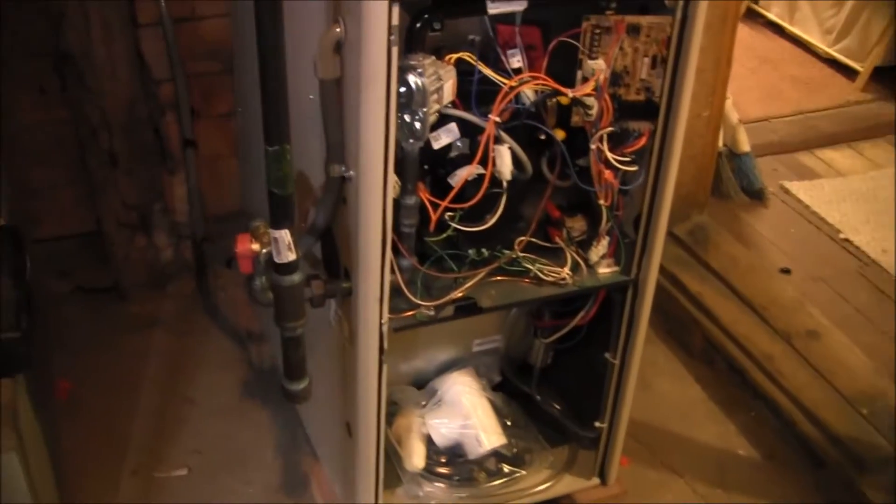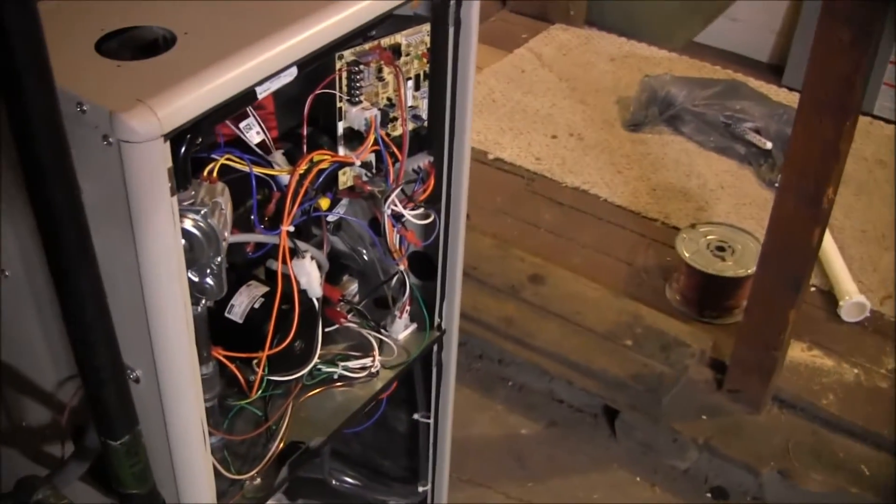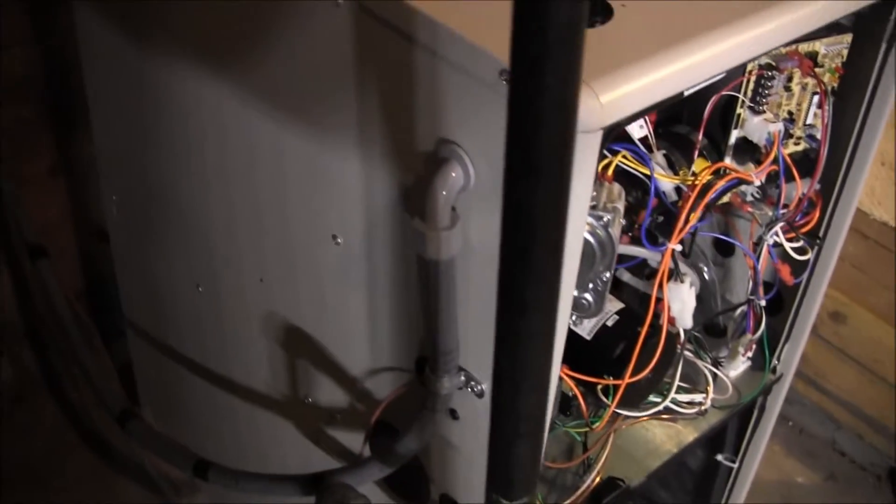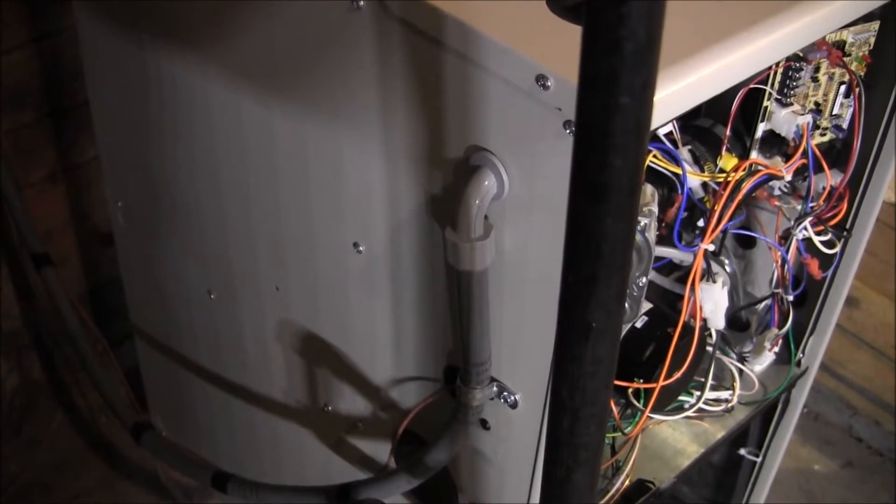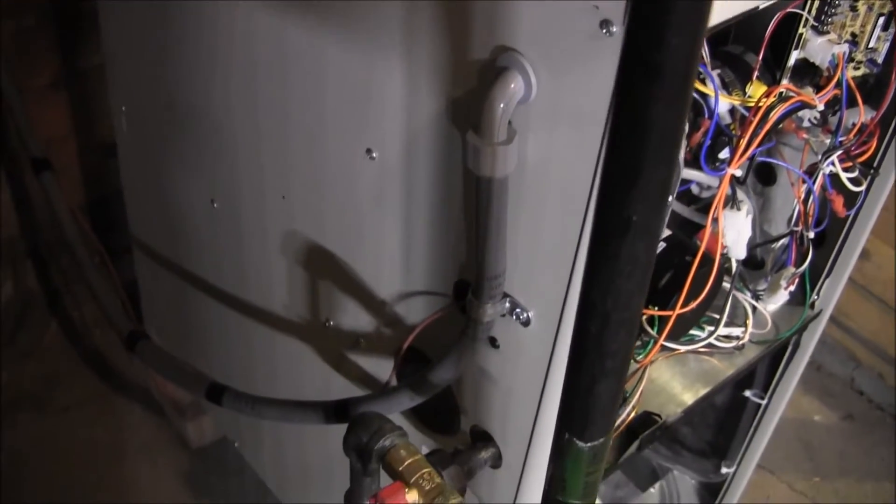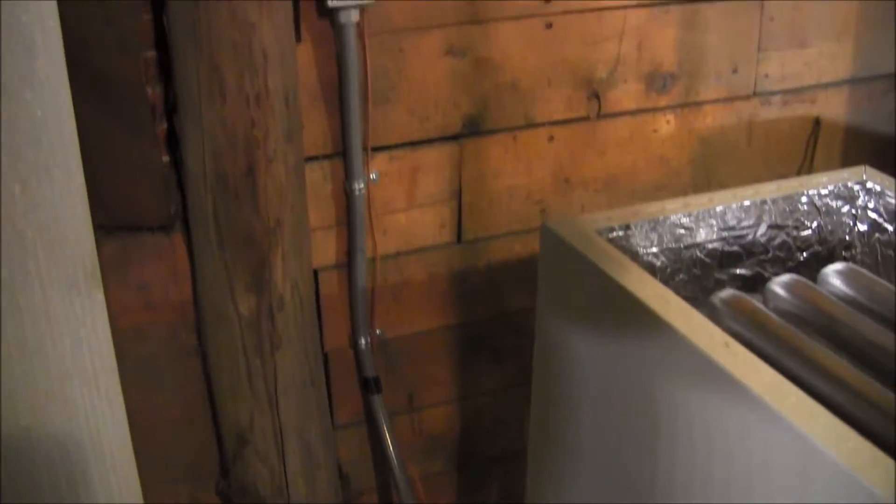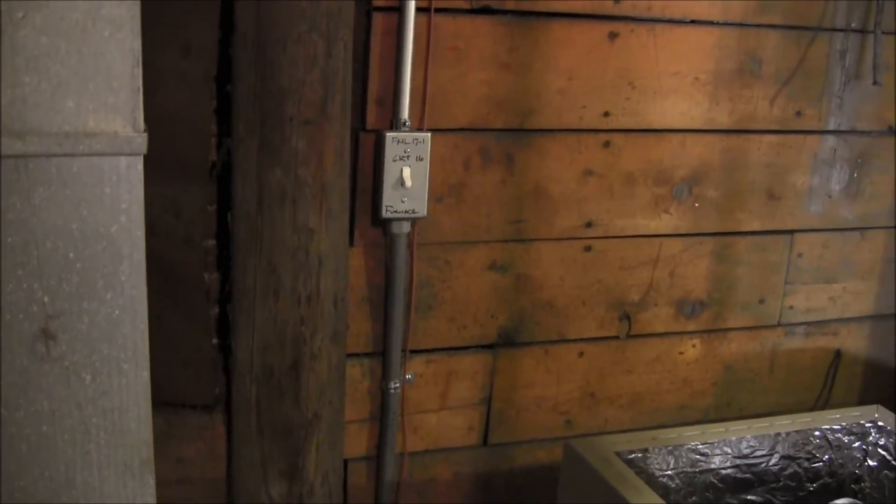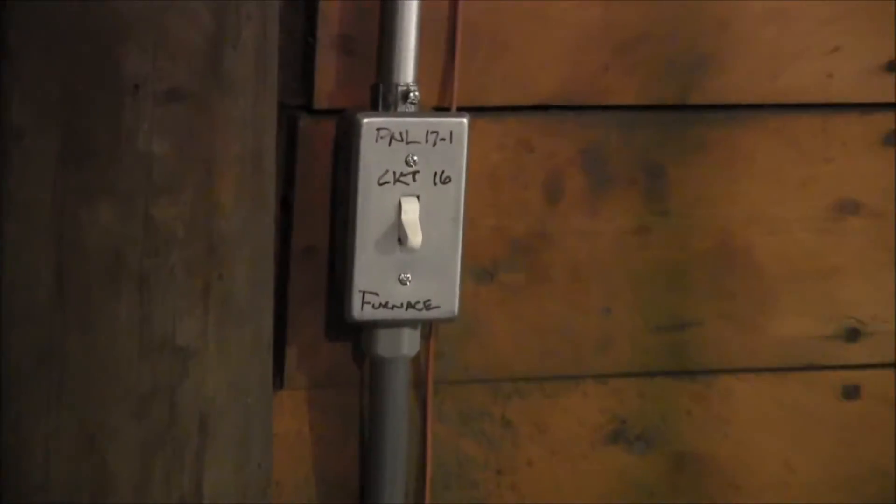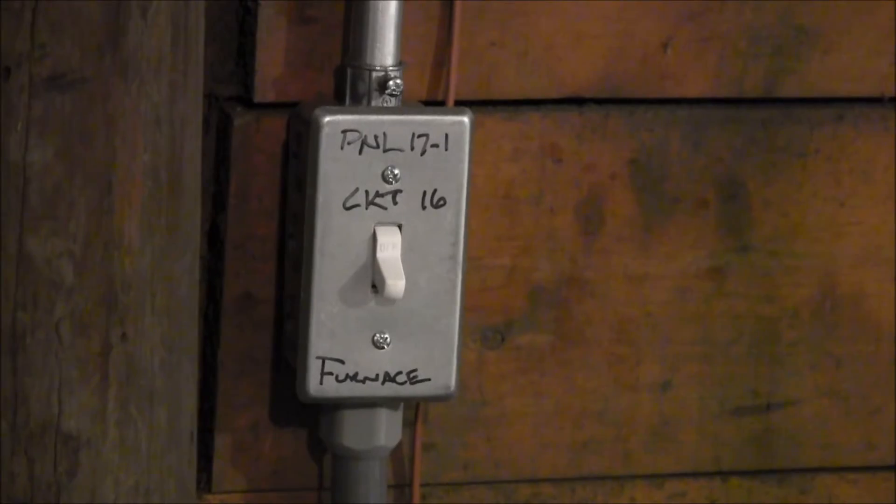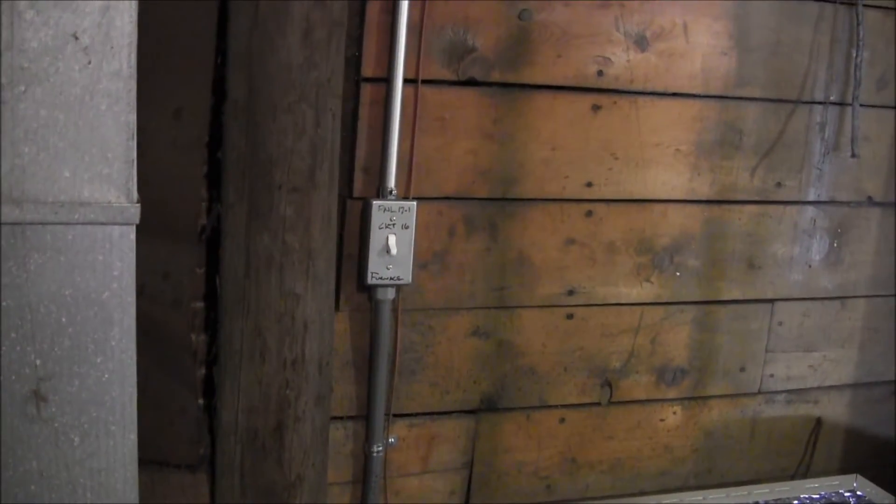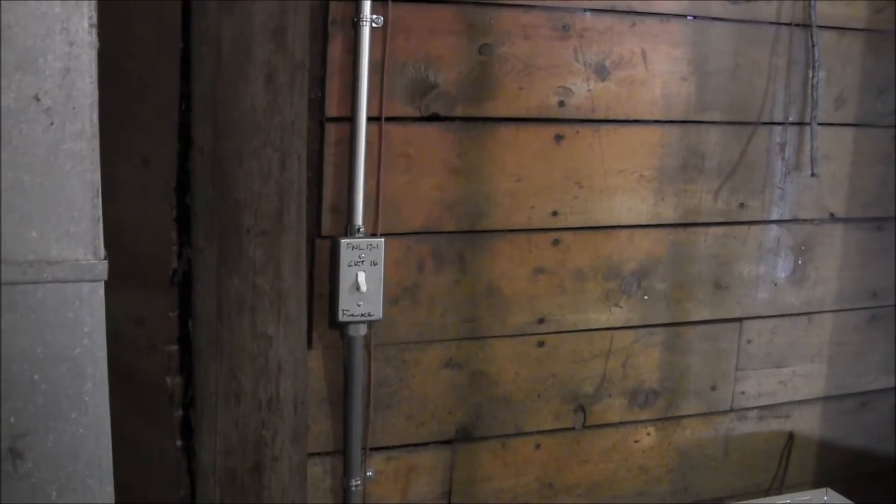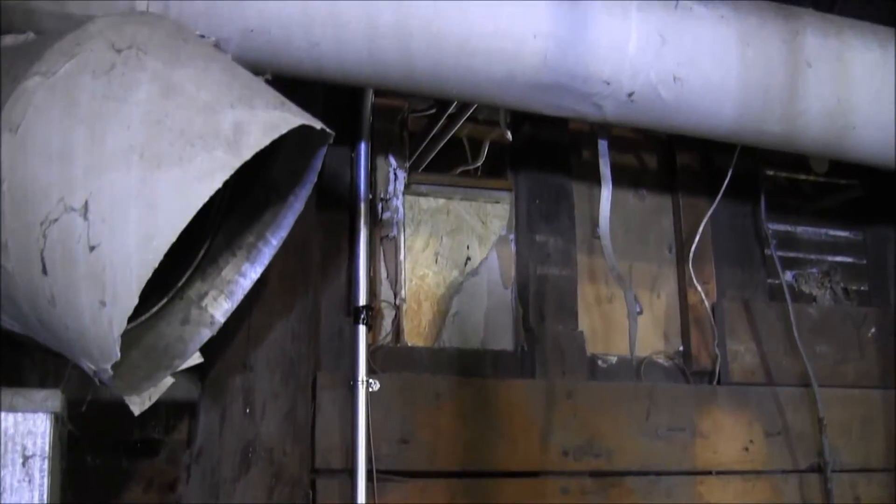So getting back to the unit. Basically, it's the same as it was in the last video. The only thing that's changed is we've added the electrical connection there. We've come out with a plastic L, dropping down into some BX, which is vinyl clad, coming up to a disconnect right here. We need a disconnect so that if anybody services the unit, myself included, you need to be able to power it down. It is not allowed that you just run over to the panel and flip the breaker.